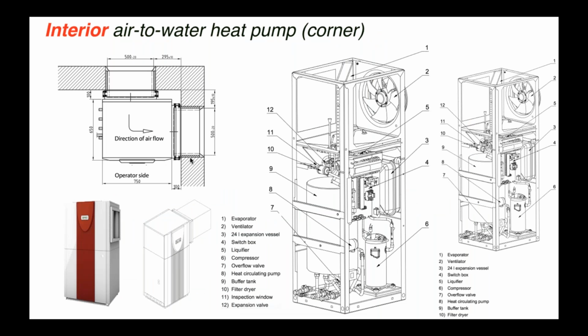Here's an example. This, I believe, is a Dimplex unit out of Germany. I want to show this. The air handling section is just the coil and the fan up here at the top. Here's your refrigeration system with a built-in buffer tank, compressor, expansion tank. And what they're doing is they're actually setting this up in the corner of a building. So they have very short ducting, probably on the order of maybe 1.5 feet of ducting, bringing air in here, running it through the air handling section, pushing it right back outside. The way they've set this up, you can configure that upper air handling section so you can go around a corner like this, or you can go straight through it.